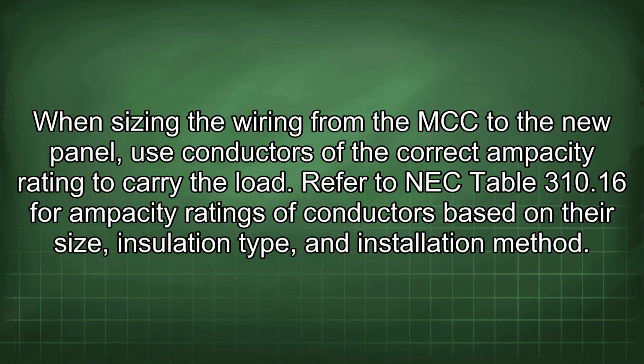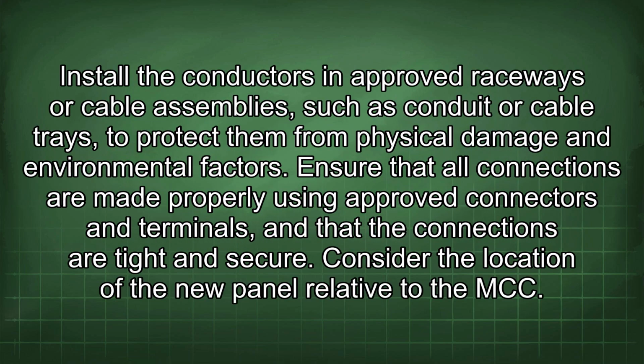When sizing the wiring from the MCC to the new panel, use conductors of the correct ampacity rating to carry the load. Refer to NEC Table 310.16 for ampacity ratings of conductors based on their size, insulation type, and installation method. Install the conductors in approved raceways or cable assemblies, such as conduit or cable trays, to protect them from physical damage and environmental factors. Ensure that all connections are made properly using approved connectors and terminals, and that the connections are tight and secure.